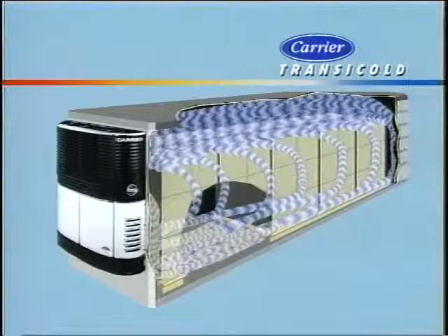Pressing the up arrow will scroll forward through the data list, bringing up readings such as the suction pressure, discharge pressure, and so on. Pressing the down arrow will scroll backwards through the list. The data will remain in the message center for 10 seconds, then return to status OK if no other keys are pressed. To lock a data item onto the display, press the equal key. The data item will flag in the message center continuously until any key on the keypad is pressed. This is helpful when wanting to watch one of the sensors while the unit is running.